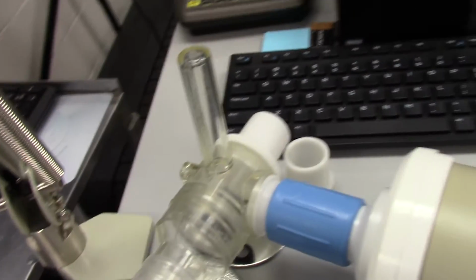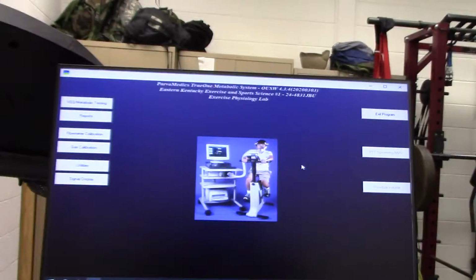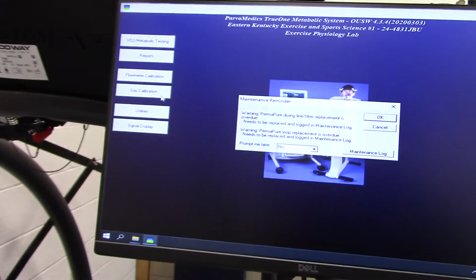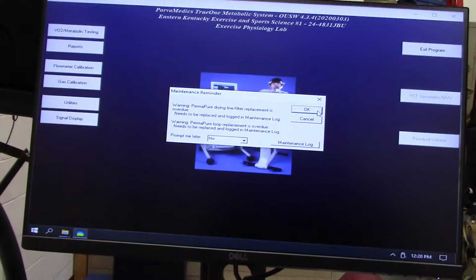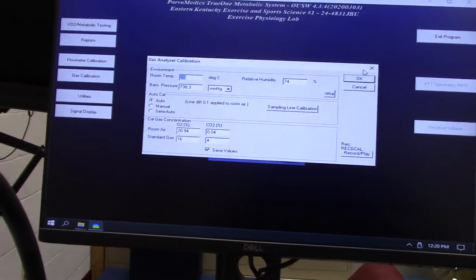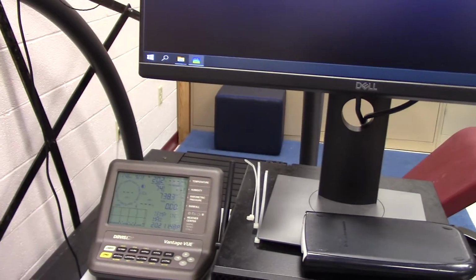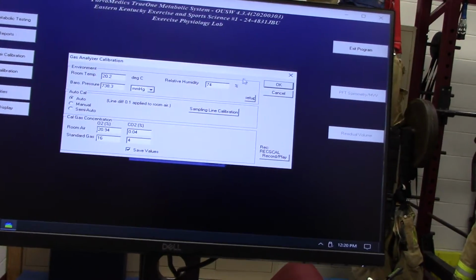Now make sure we obviously have these valves set up appropriately before we run and everything's linked up correctly. From there, we're going to go to our gas calibration. Yep. Making sure that everything's being done correctly. Temperature, oh, we're up to 20.2. Is the AC functioning in the building? Now I'm getting concerned that it might not be.